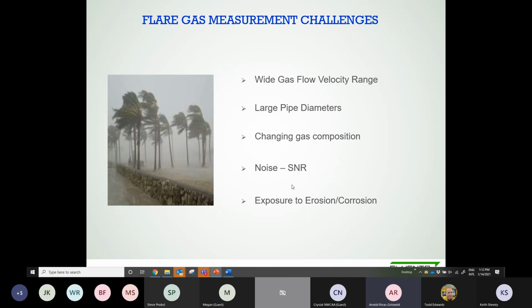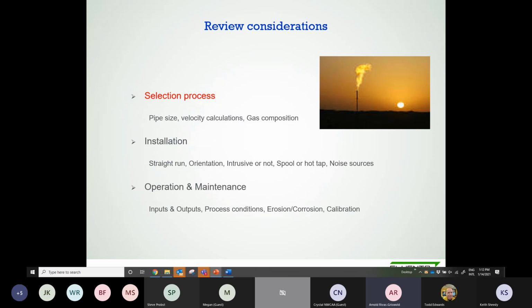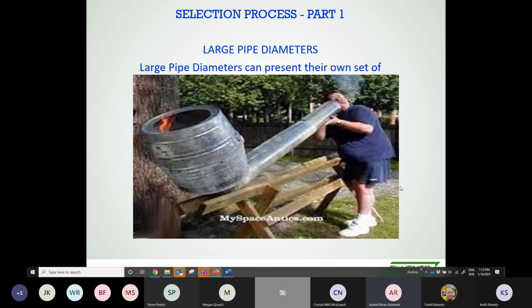When it comes to ultrasonic measurements, which is what Fluenta focus on, there's also noise and noise considerations and the signal to noise ratio that we have to take into account when it comes to our measurements. So that's something that has to do with the velocity and the properties of the gas that's going through the pipe. And of course, everything that you use to measure will be exposed to erosion and corrosion based on the fluids going through the pipe. So some considerations, for example, in the selection process would be, like I mentioned, the pipe size, velocity calculation, and gas composition. So let's take a look at those in detail.